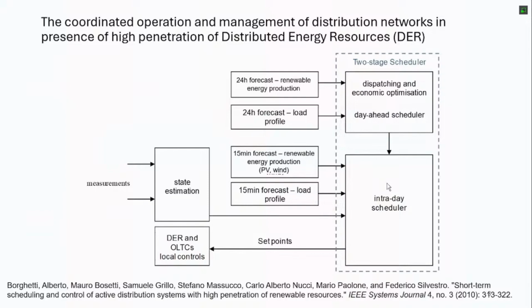The intraday scheduler acts in general on the on-load tap changer, or LTC, so the transformer can change its ratio of operation during the day, and also on some local controls, such as capacitor banks. But in particular, we think that the distributed energy resources can be controlled, so we can change the voltage, the reactive and also the active power of the available resources under the control of the distribution system operator.